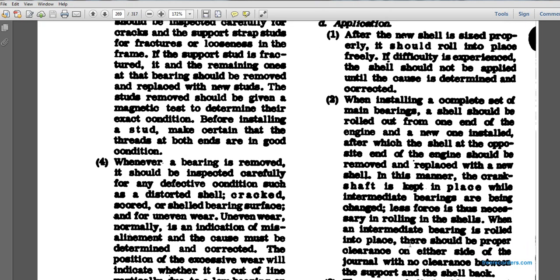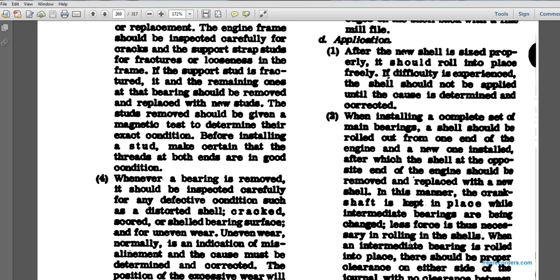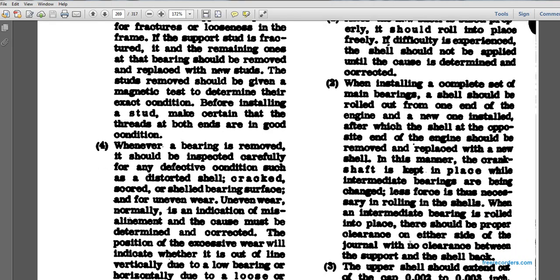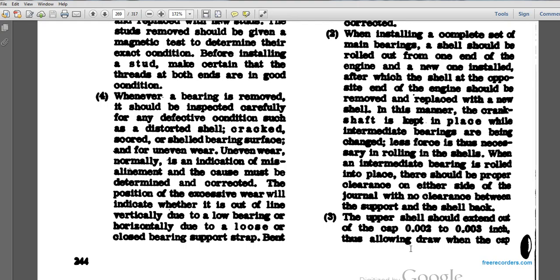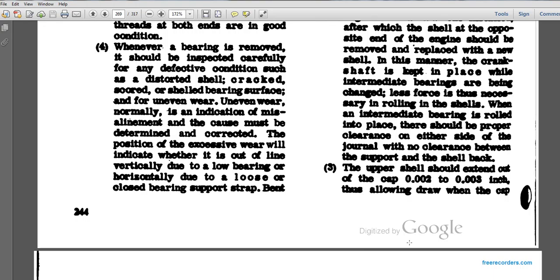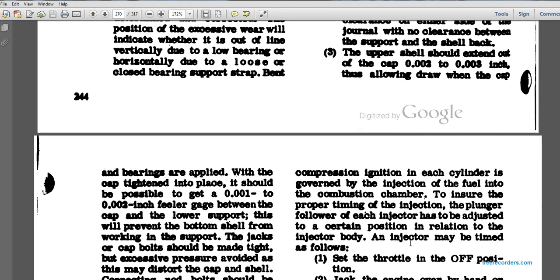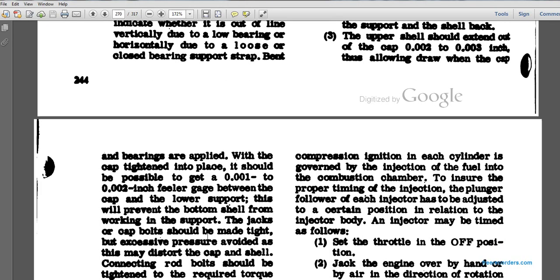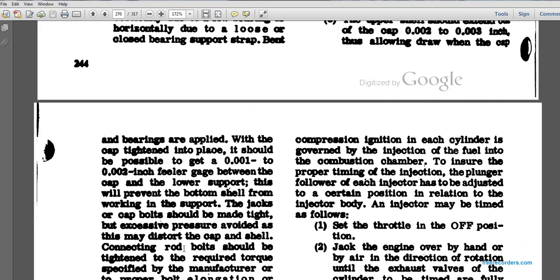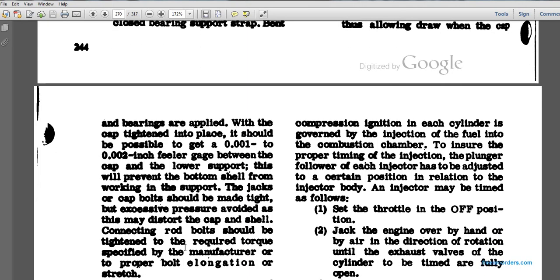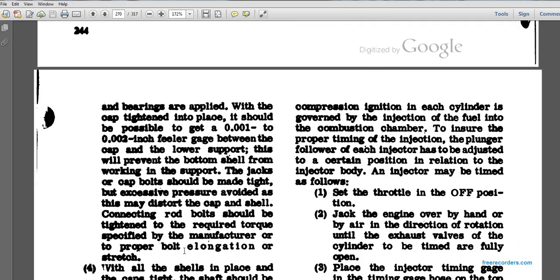When the intermediate bearing is rolled into place, there should be proper clearance on either side of the journal, with no clearance between the support and the shell back. The upper shell should extend out of the cap about 2/1000 to 3/1000 of an inch, allowing the draw within the cap for bearings that are applied. With the cap tightened into place, it should be possible to get a 1/1000 or 2/1000 inch feeler between the cap and the lower support. This prevents the bottom of the shell from working in the support. The cap bolts should be tight, and excessive pressure avoided as this may distort the cap and the shell. Connecting rod bolts should be tightened to the torque specified by the manufacturer for proper elongation and stretch.